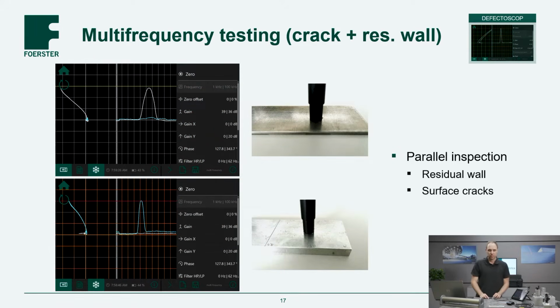The next testing task we will have a look at, which is also the last for the vector scope, is multi-frequency testing. When we do multi-frequency testing, we can use the probe for different kinds of applications in parallel. That means we make a setup where this probe we used before is optimized for the residual wall testing, and we additionally do a setup where it is optimized to test for cracks. So we can test in parallel for residual wall and for small surface cracks. And that we will also look at live.